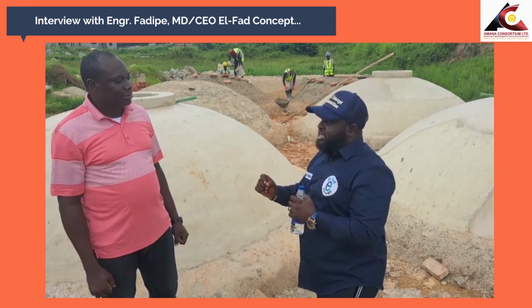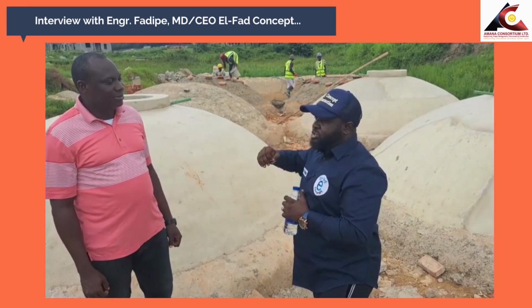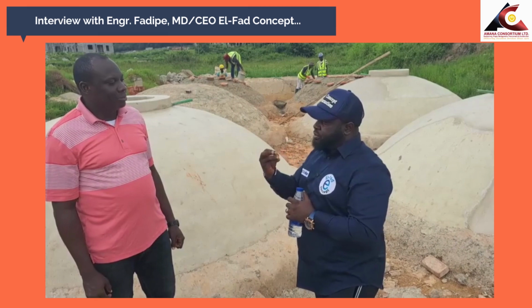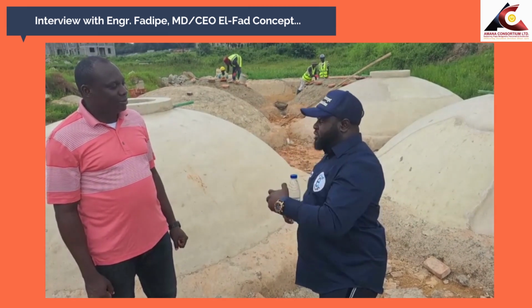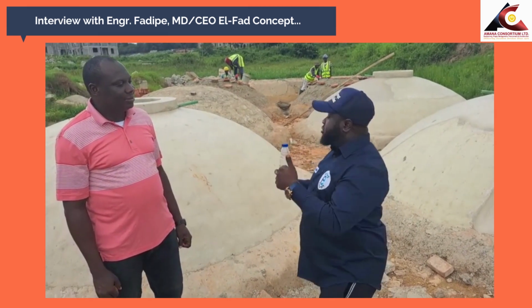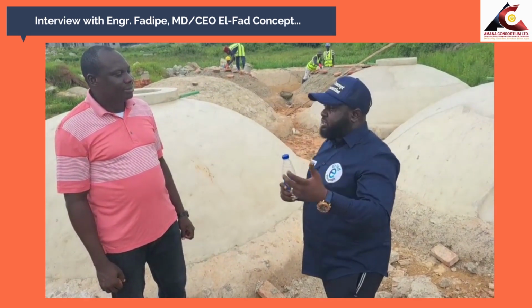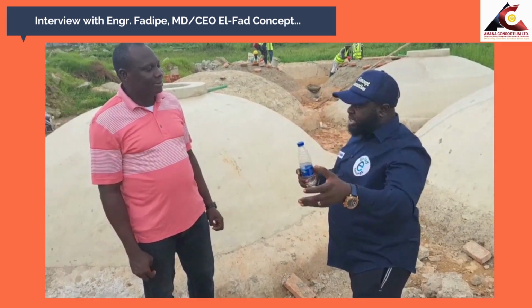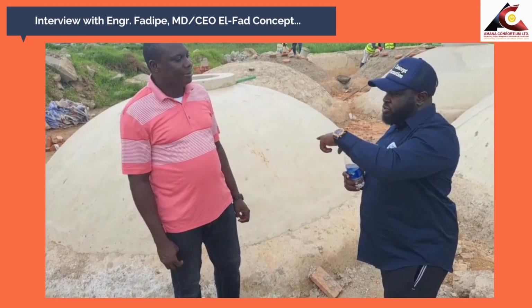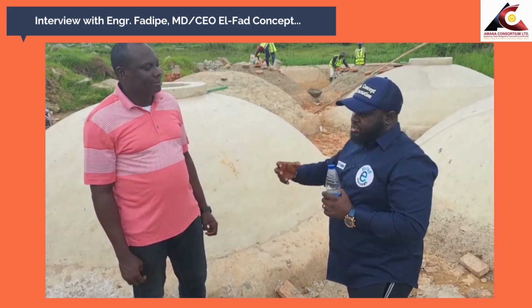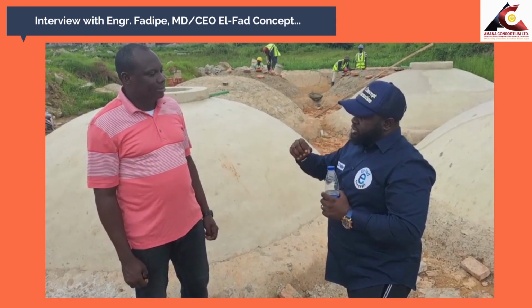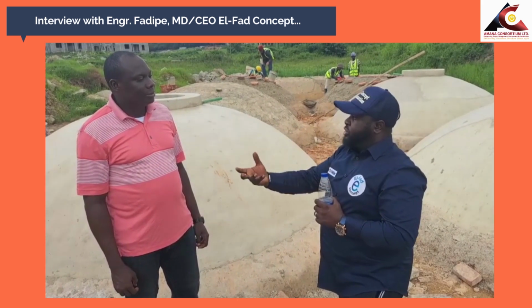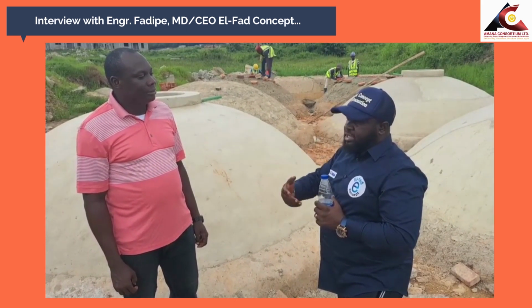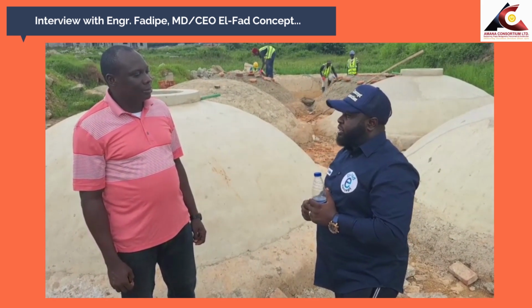Now this is the key. Every organic waste can be introduced into it, even leftover food. So every waste is a resource, and at the end of the day, you can even use the gas for heating or sterilization of your equipment. What we need to do is to desulfurize the biogas so that the hydrogen sulfide content does not corrode your generator, and you have clean methane, and of course you can now use it to power your system.